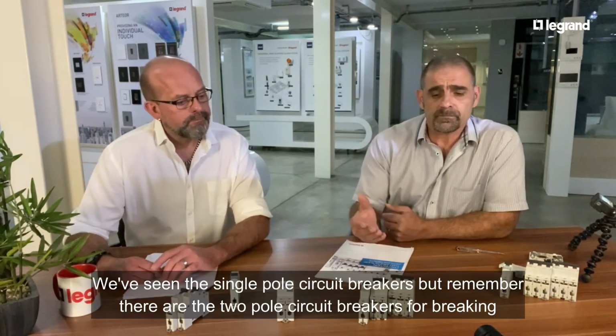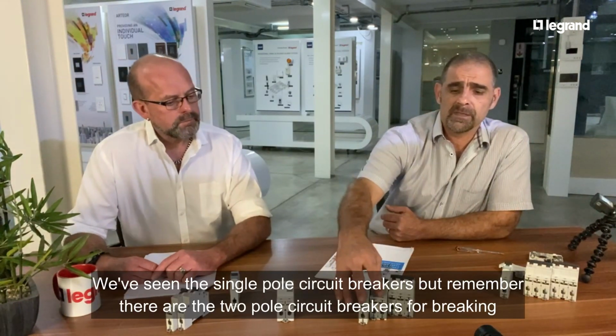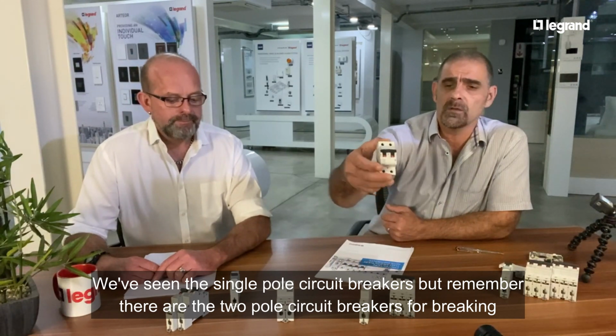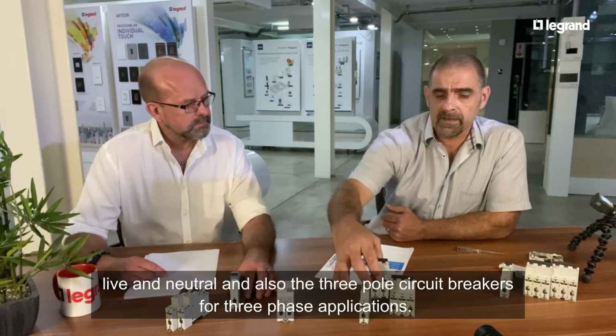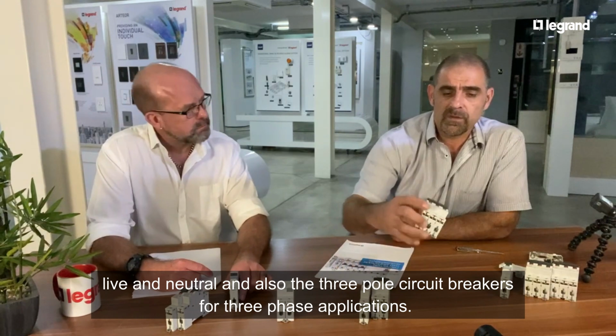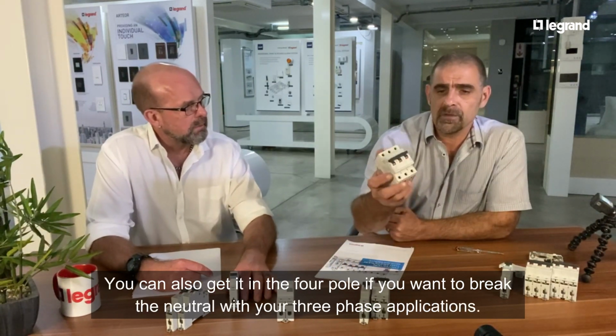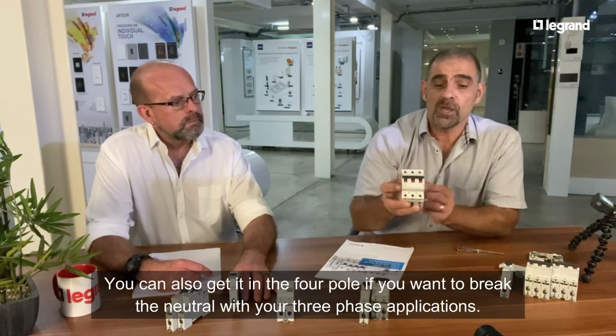I've shown you the single pole circuit breakers, but remember there are two pole circuit breakers as well. They are for breaking live and neutral. And then we have the three pole circuit breaker for three phase applications. You also get it in a four pole if you want to break the neutral with your three phase applications.